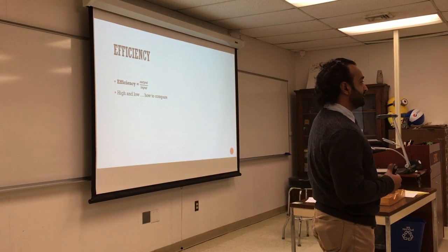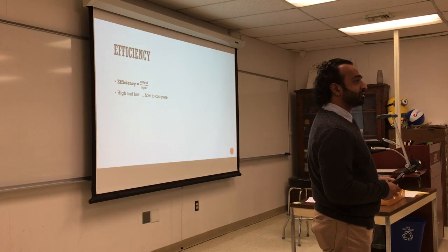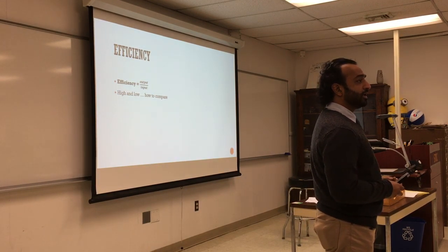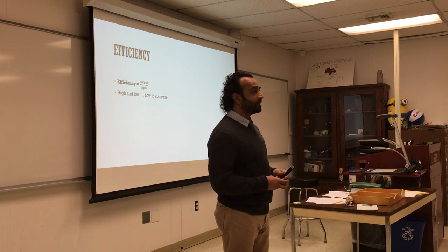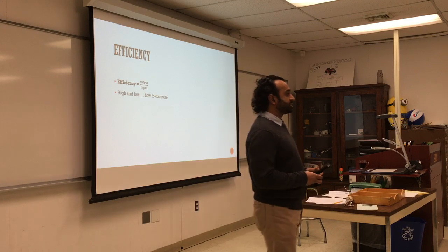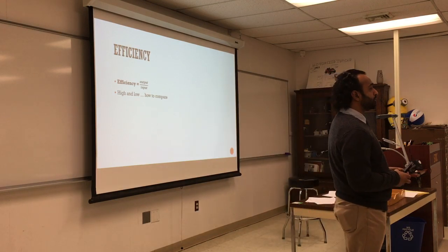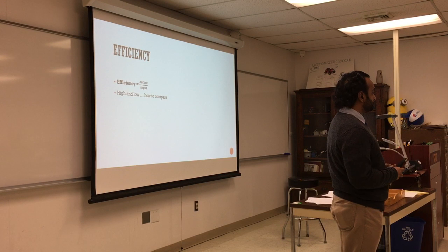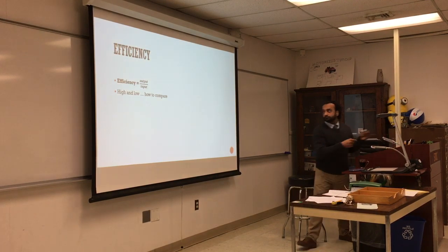When they say it's 97% efficient, they do not mean combustion efficiency, that's thermal efficiency. Combustion efficiency is how much heat you get out of the fuel. So I'll write it down so you have this distinction. There's combustion and thermal efficiency.